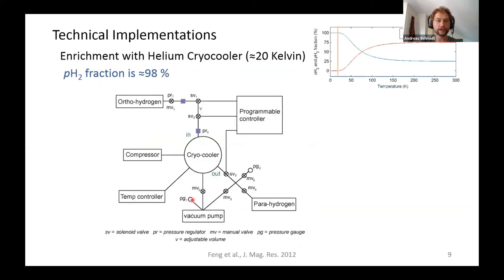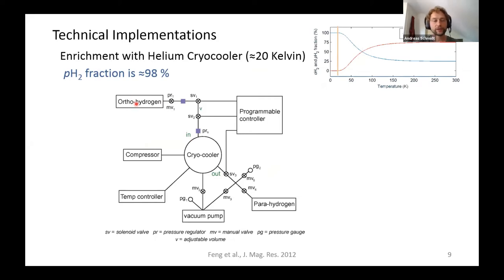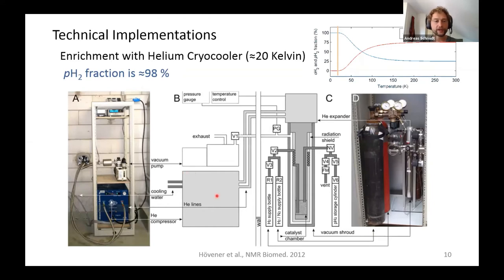If you want maximum enrichment, you go to even lower temperatures — close to 20 K. The approach is the same: room-temperature hydrogen with 25% parahydrogen enters a cryo-cooler based on a helium compressor and expander, cools to 20 K, contacts an iron oxide or activated charcoal catalyst, and upon exiting yields ~98% parahydrogen enrichment, as experimentally demonstrated.